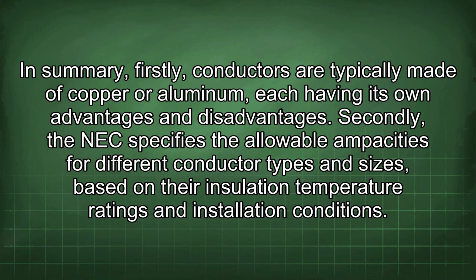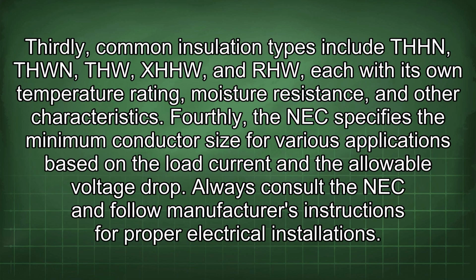In summary, firstly, conductors are typically made of copper or aluminum, each having its own advantages and disadvantages. Secondly, the NEC specifies the allowable ampacities for different conductor types and sizes based on their insulation temperature ratings and installation conditions. Thirdly, common insulation types include THHN, THWN, THW, XHHW, and RHW, each with its own temperature rating, moisture resistance, and other characteristics. Fourthly, the NEC specifies the minimum conductor size for various applications based on the load current and the allowable voltage drop. Always consult the NEC and follow manufacturer's instructions for proper electrical installations.